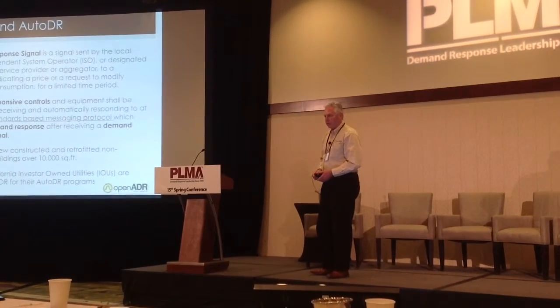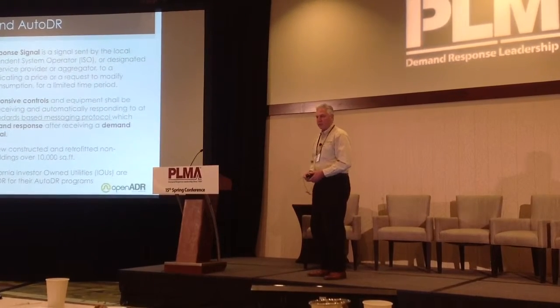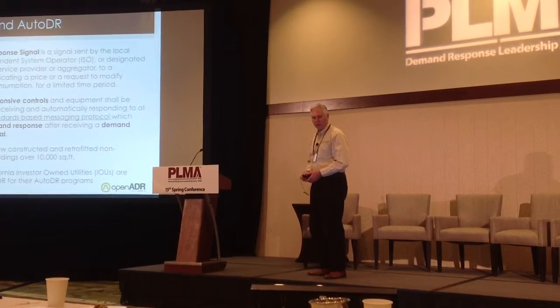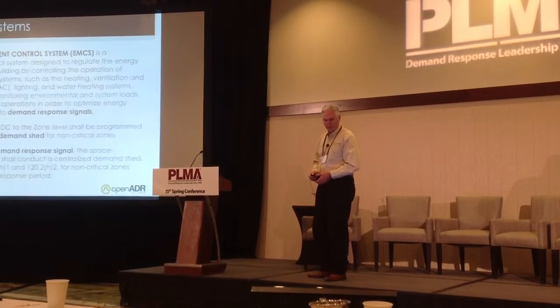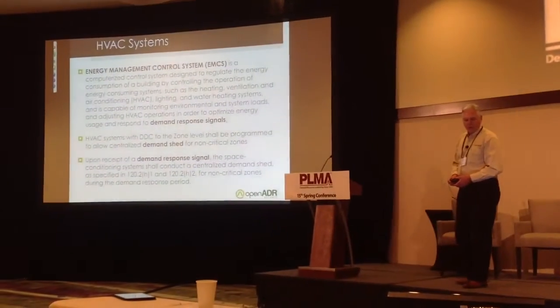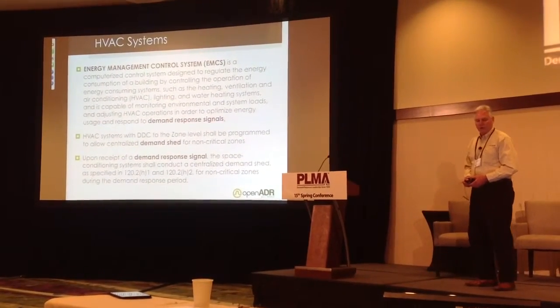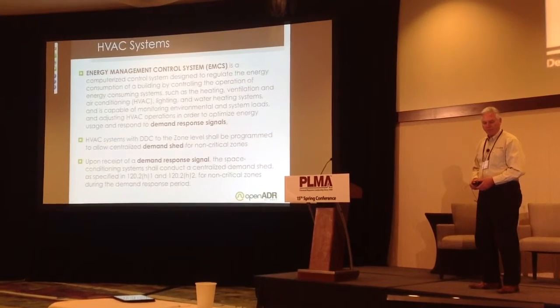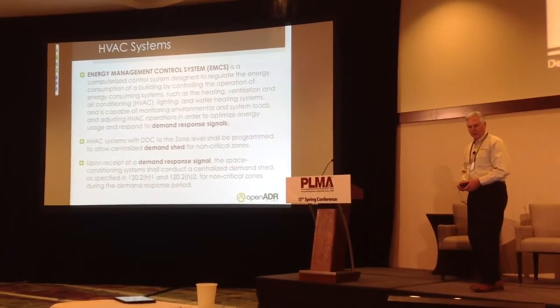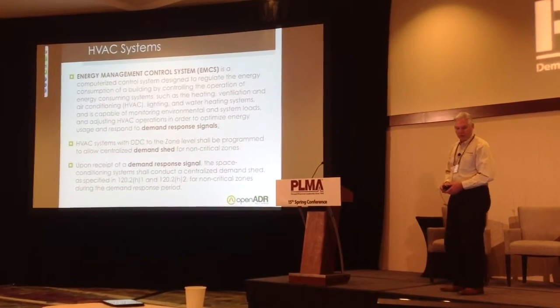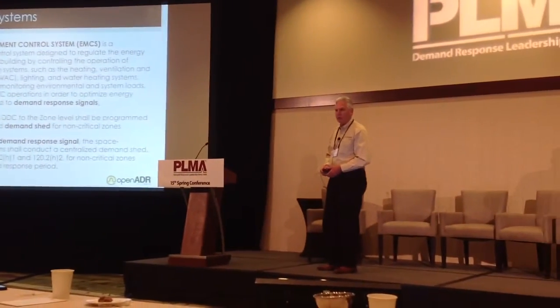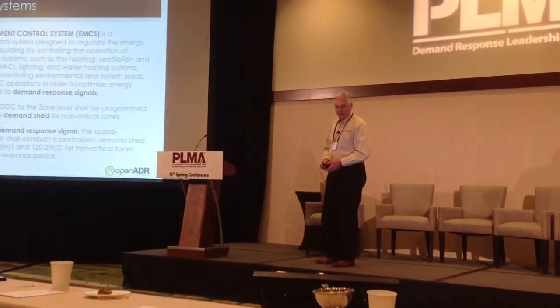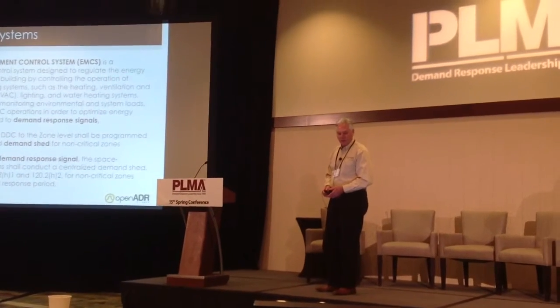The code doesn't prescribe that the customer participate in a program — it's just that the equipment needs to have the auto DR interface. We're seeing that in energy management control systems and HVAC systems with DDCs and zone-level controls. Equipment needs to be able to shed demand at the zone level.